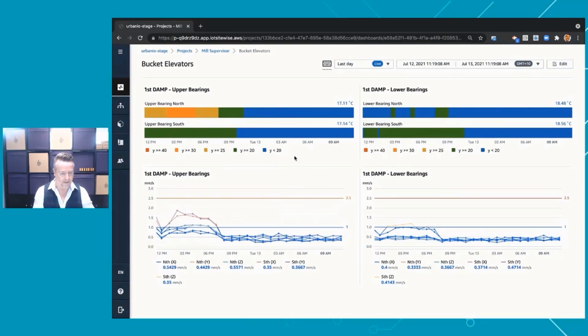Really what we're looking for here is a temperature anomaly. If something gets hot, that's bad, obviously - that's the thing we're trying to detect, an ignition point. Vibration is an early warning, an indicator of when things are moving, and it can also indicate friction is occurring, which will then raise temperature. You can actually see it here, where the vibration is just going over 1 millimeter per second when activity happens, and the temperature is heating up at that point.